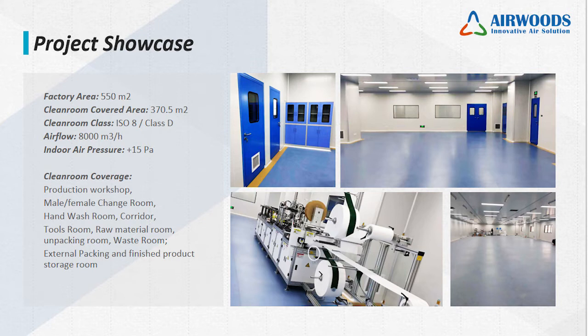Tom, could you show the layout? Yeah, you can see the layout. There are 5 production lines. It is an ISO-8 ductless clean room with an air change rate of 25 times per hour. The indoor pressurization is about 15 to 20 Pascal, positive pressure.